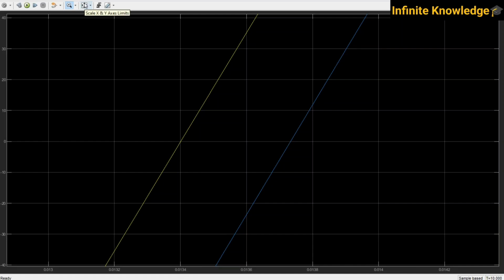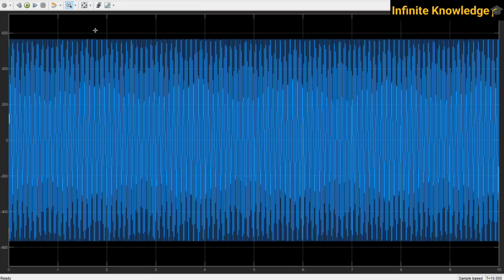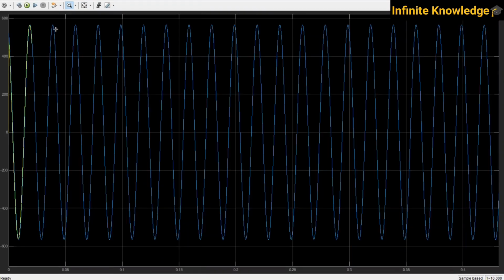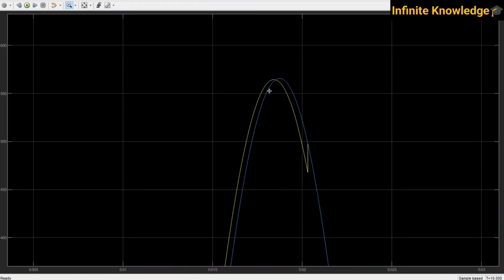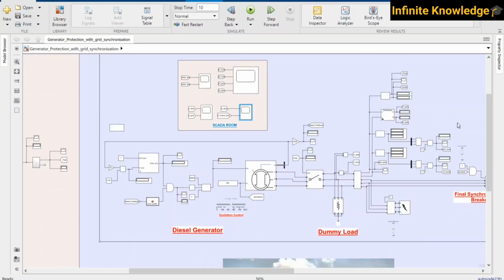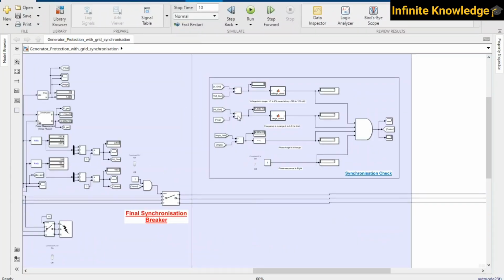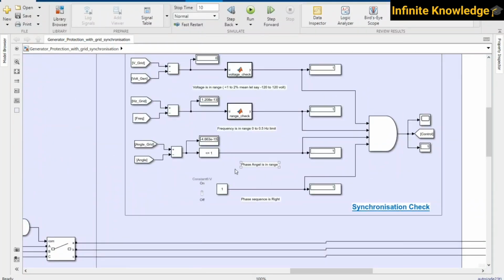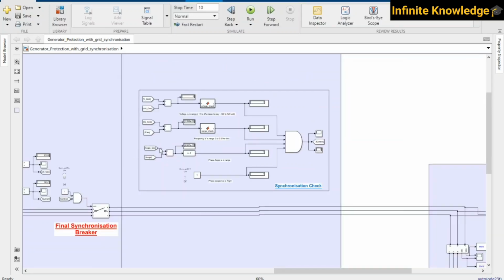So we are very near to our supply voltage, and at this condition, which is very satisfactory to synchronize, we have synchronized. So finally only one signal is there, and both voltages overlap each other. So what is the condition of the voltage phase angle? It will be less than 1, and we are at 0.001. We are in a very good condition.